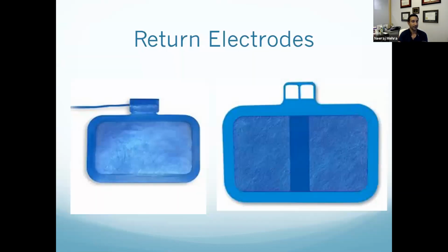Now, in our circuit, we don't just have a water pump that's pumping up to the ground and flowing out into nowhere. We actually want to capture that water back. We want to capture those electrons back. And so we have these, which are not grounding pads - grounding pad is the wrong term. These are called return electrodes. A grounding pad means the electricity or current is being pumped out into the patient and then to the ground and out of the way. That's not what our pump is doing. Our pump doesn't want to waste all this water, or all this electricity. It doesn't want it leaking anywhere.